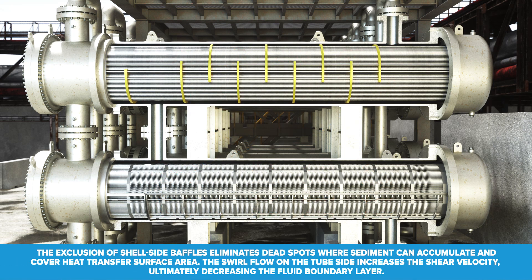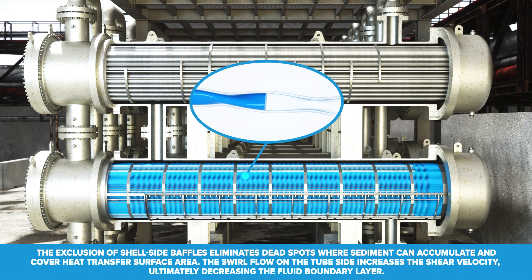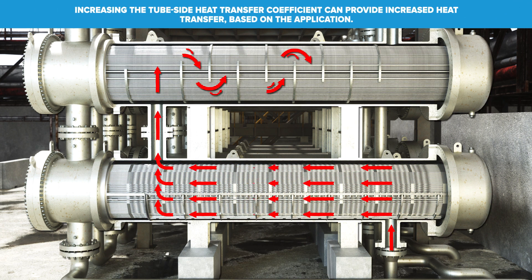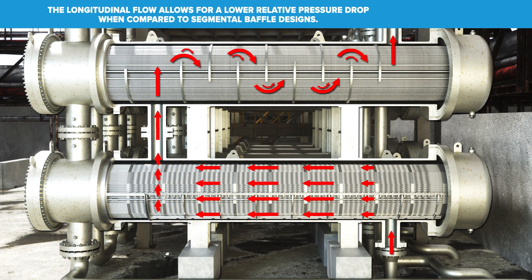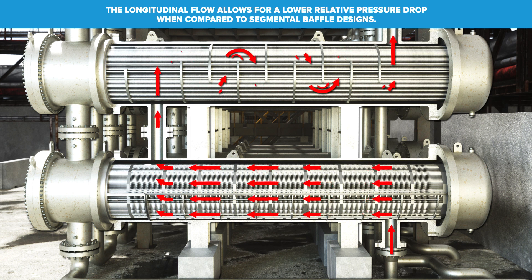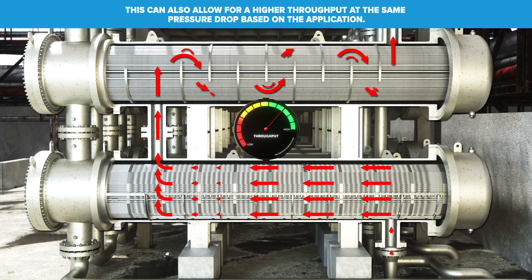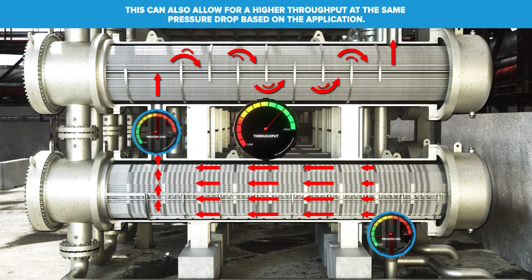The exclusion of shell-side baffles eliminates dead spots where sediment can accumulate and cover heat transfer surface area. The swirl flow on the tube side increases the shear velocity, ultimately decreasing the fluid boundary layer. Increasing the tube side heat transfer coefficient can provide increased heat transfer based on the application. The longitudinal flow allows for a lower relative pressure drop when compared to segmental baffle designs, and can also allow for higher throughput at the same pressure drop based on the application.